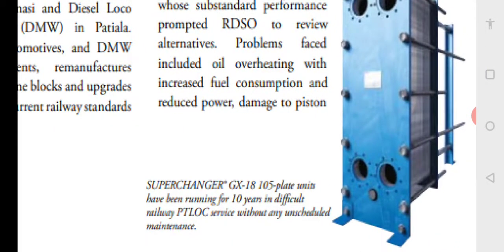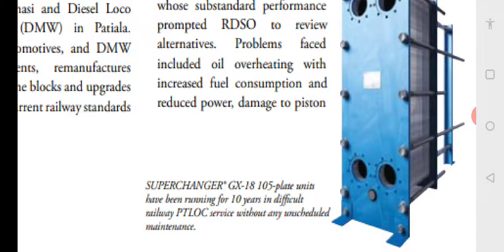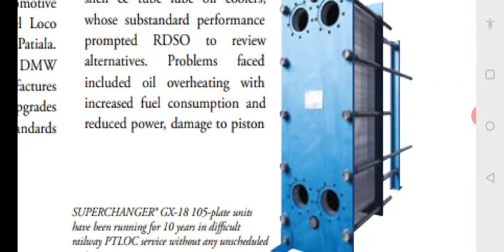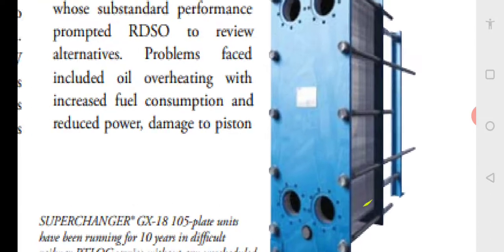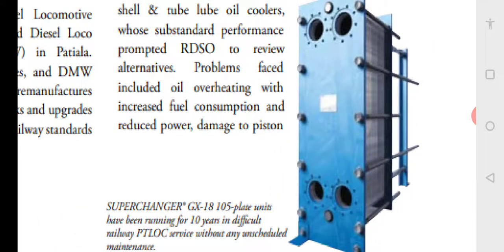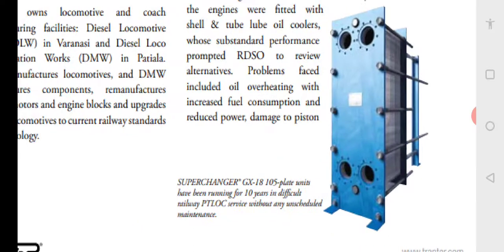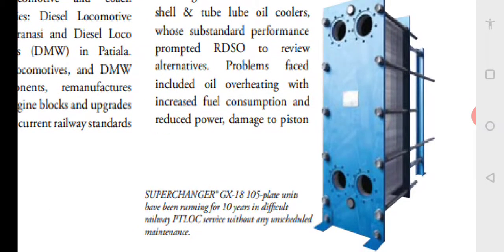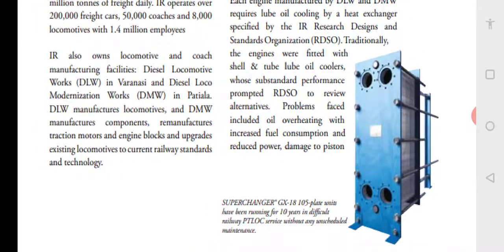The Tranter Super Changer GX-18 with 105 plate units has been running for 10 years in difficult railway conditions. In railways, it is called PTLOC — Plate Type Lube Oil Cooler — and it requires virtually no maintenance. The end plates are visible — blue color painted — and inside are stainless steel plates held together by rods. Dismantling is very easy: remove the nuts at the ends, remove the rods, and all plates can be dismantled. They can be cleaned using a wire brush, hot water, and chemicals, then reassembled using new gaskets — only the gaskets need replacing.